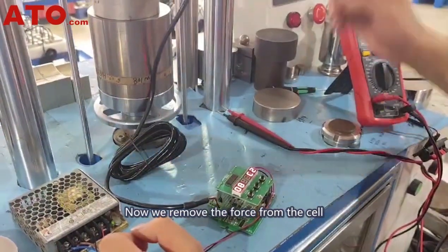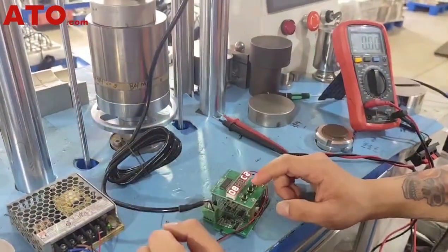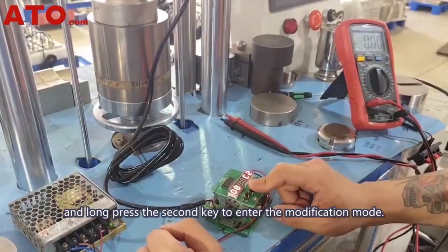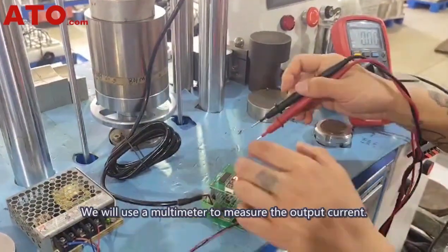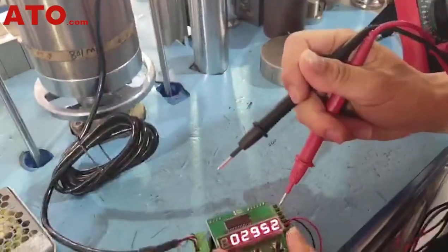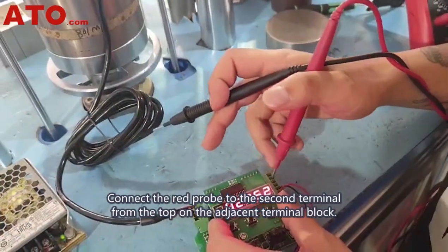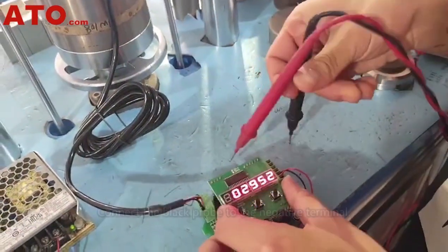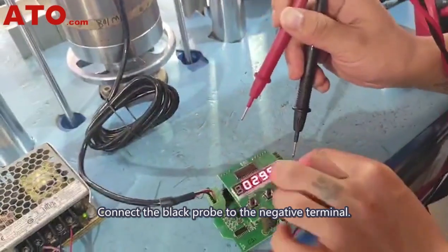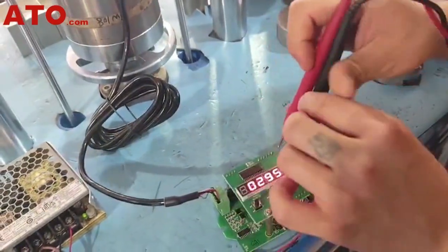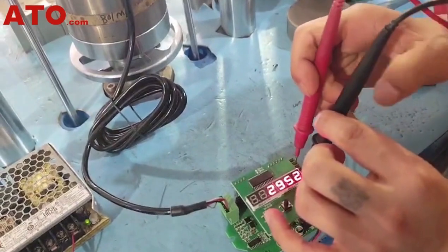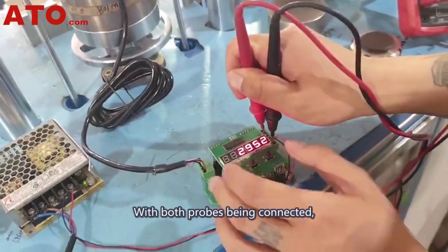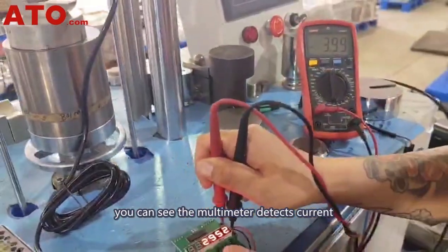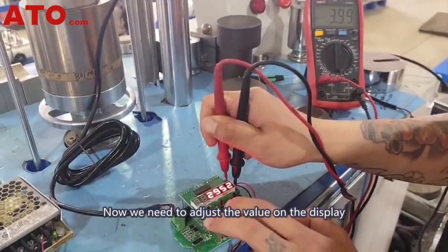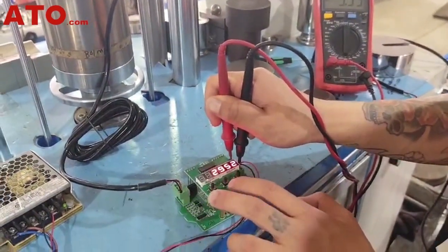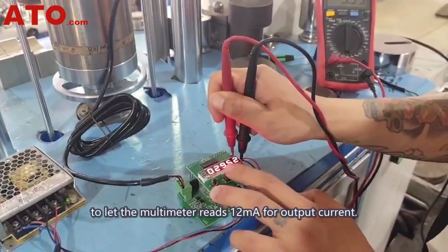Now we remove the force from the cell, and long press the second key to enter the modification mode. We'll use a multimeter to measure the output current. Connect the red probe to the second terminal from the top on the adjacent terminal block. Connect the black probe to the negative terminal. With both probes being connected, you can see the multimeter detects current. Now we need to adjust the value on the display to let the multimeter read 12 milliamps for output current.